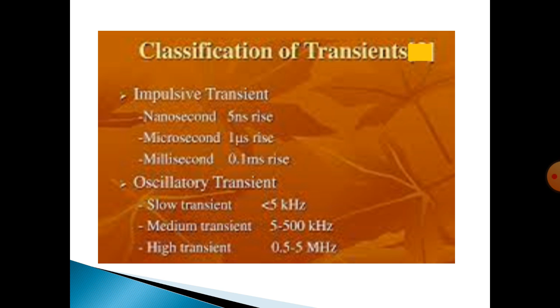And this is the main thing about impulsive and oscillatory transients. Impulsive transients have unidirectional polarity, but oscillatory transients have both negative and positive polarity. That means they are bidirectional in polarity. An example of oscillatory transients is capacitor bank energization.